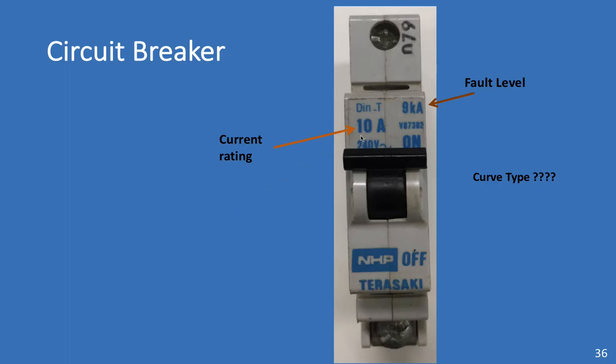So we have a current rating which is the most important thing. And we have a fault level rating. You'll notice there's nothing here to tell us what kind of trip curve or curve type this circuit breaker has. And if it doesn't tell us, then we have to assume it's a C curve trip. So, without any other information, we're going to have to consider this a C curve.